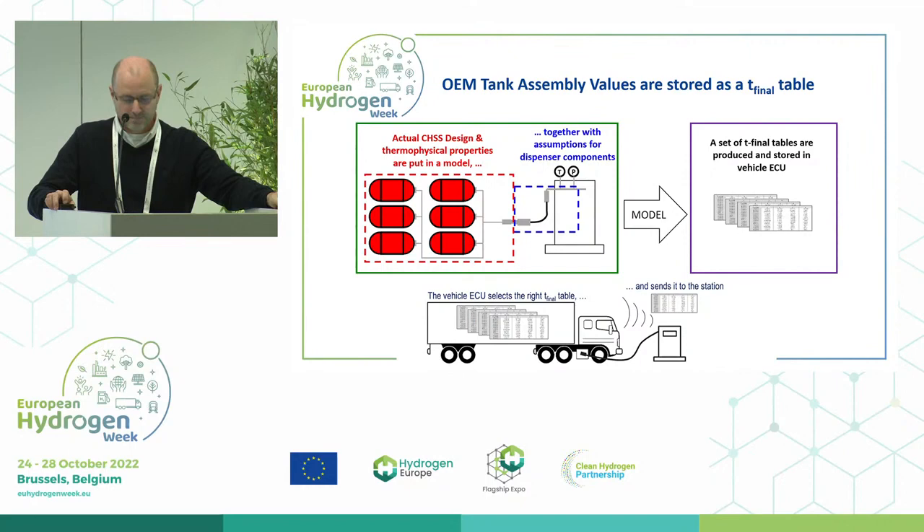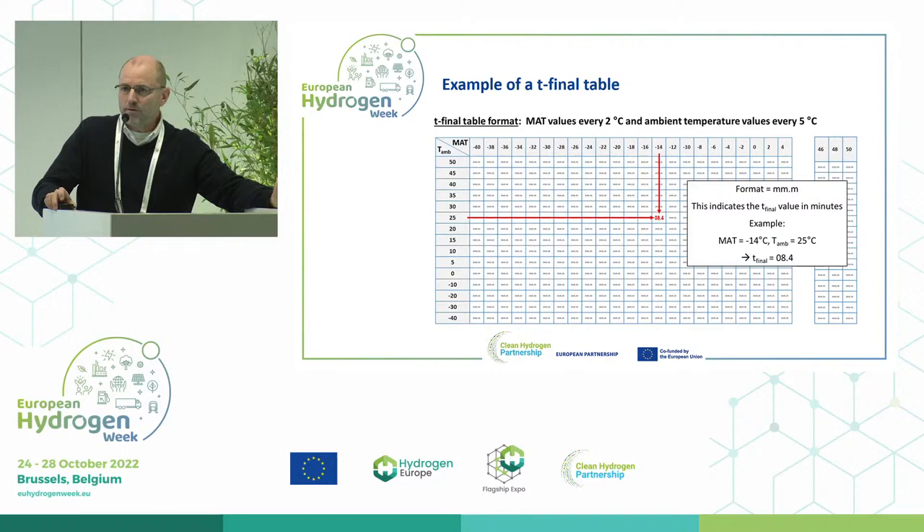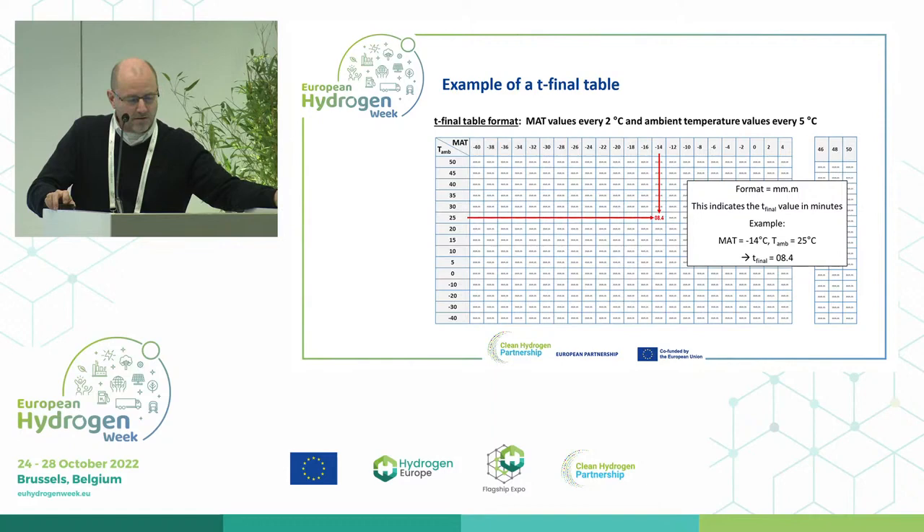What does a T-final table look like? It is a simple table showing in minutes how long the fueling should take. On the Y-axis you can see the ambient temperature — the warmer the ambient temperature, the longer it will take. On the horizontal axis there will be the MAT value, the mass average temperature, which is mainly based on the dispenser temperature. The colder you fuel, the faster you can fuel.